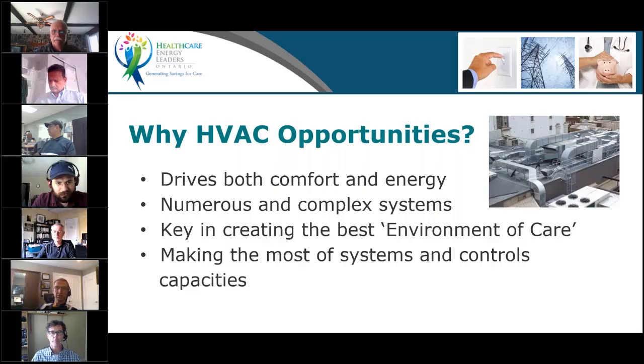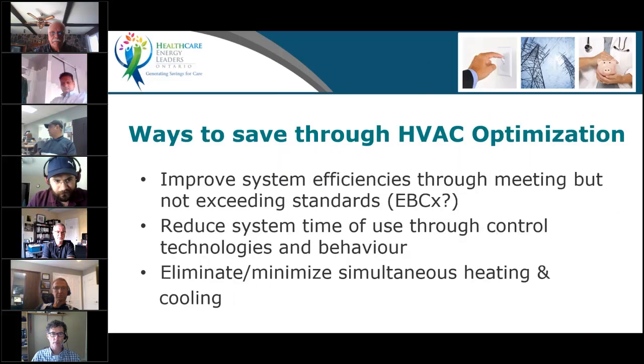So, HVAC opportunities, and I'm talking about what I call the frontline system. Those are the systems that really dictate most of your comfort condition, because they provide the heating and the cooling in large part to your spaces, and obviously the ventilation. And when I say ventilation, that's fresh air ventilation, as well as the air changeover that's required in healthcare. So they are very critical in establishing the comfort condition, obviously the energy usage, and you have to optimize the way you use the equipment in place.